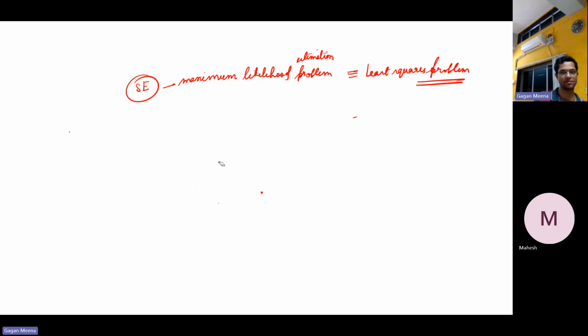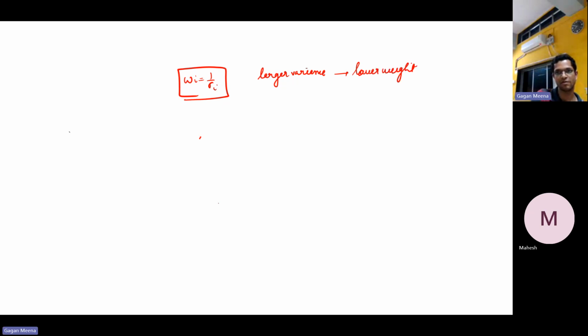And we will see one problem for this. So it is solved as a least square problem. In the traditional transmission system, state estimation is a non-linear one. So it is a non-linear least square problem, which is derived from the maximum likelihood estimator. And here we assign different weights, Wi, where W is the weight for each of the measurements. The measurements which have larger variance have a lower weight because their sigma is high. Sigma is the standard deviation here. The measurements that have higher variance are assigned less weight because we have less confidence in measurements having larger variance.